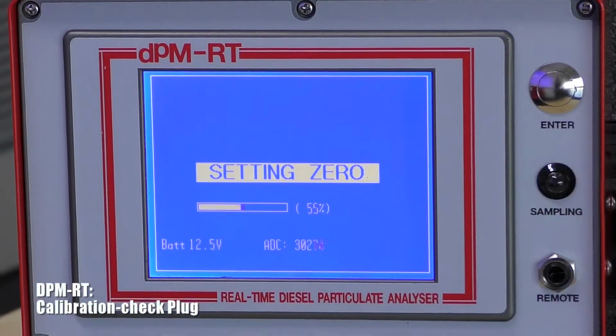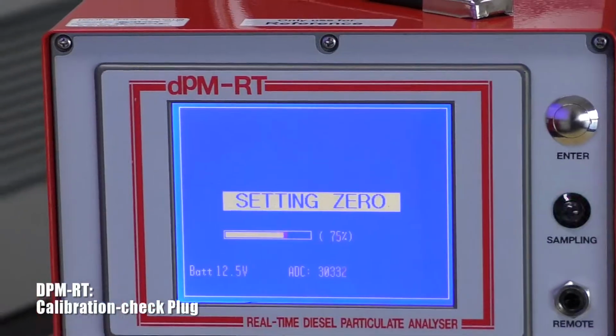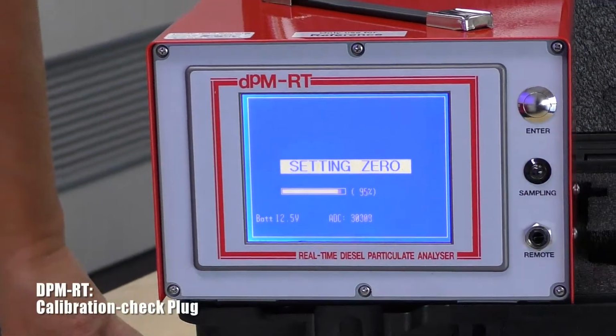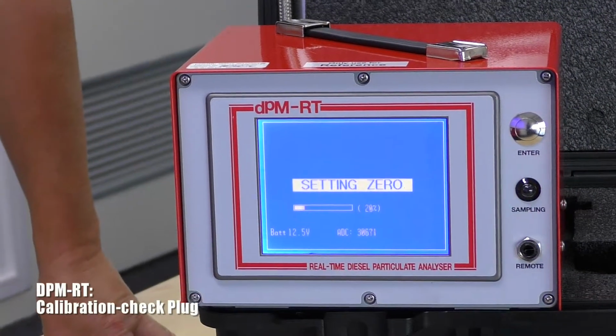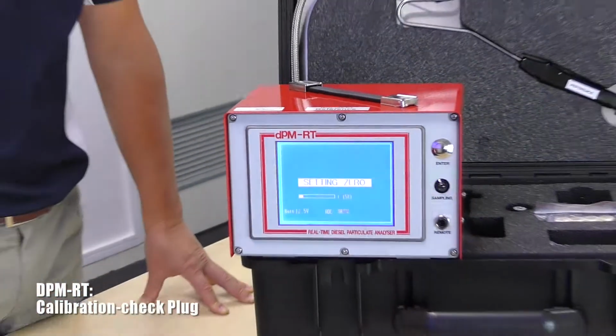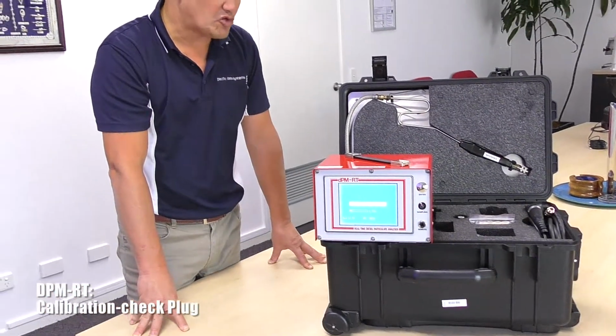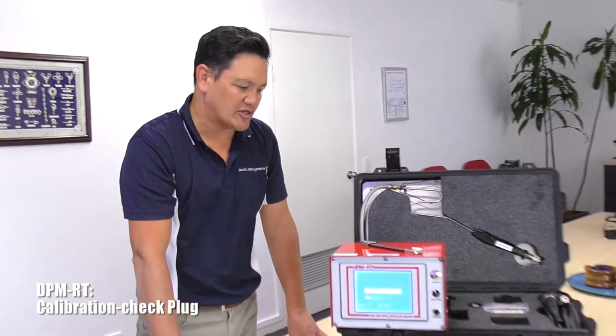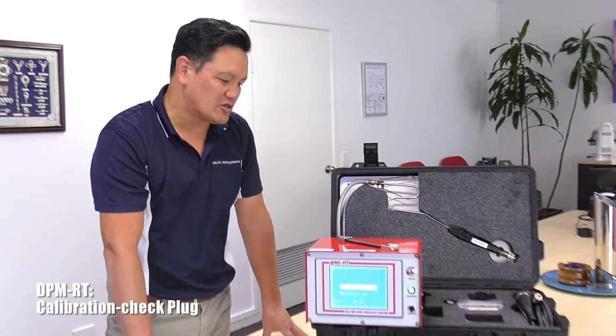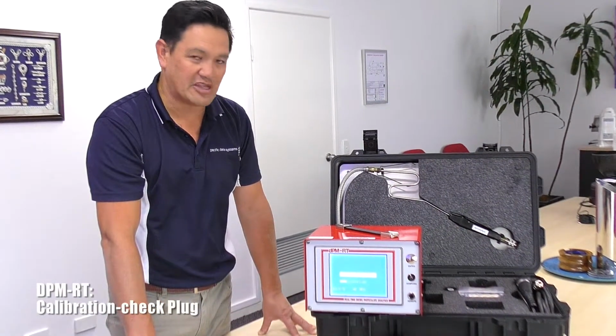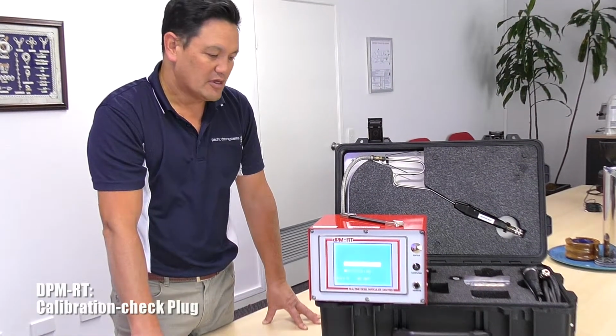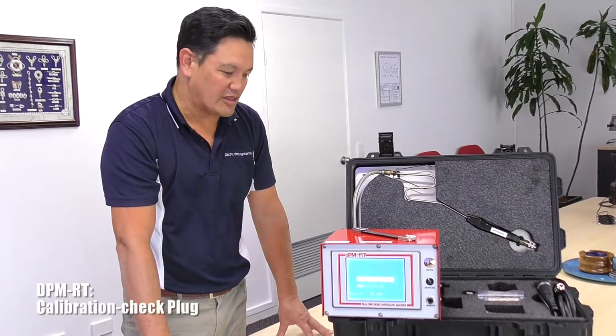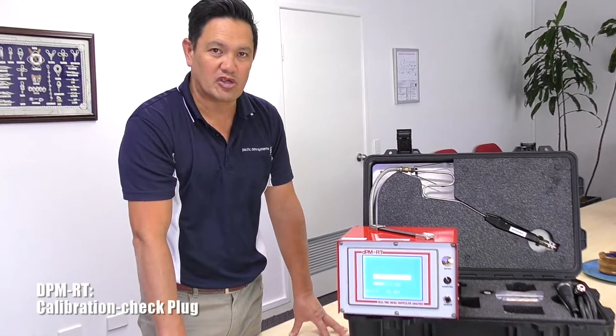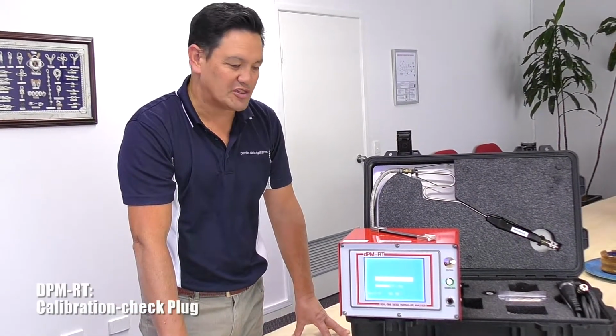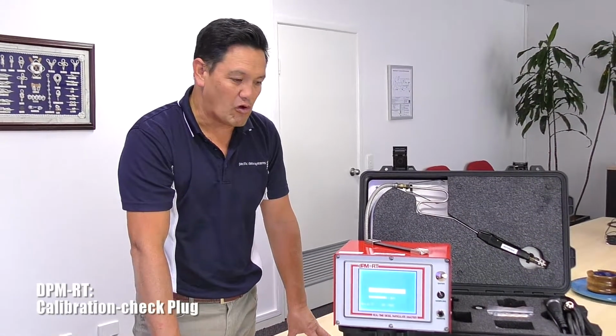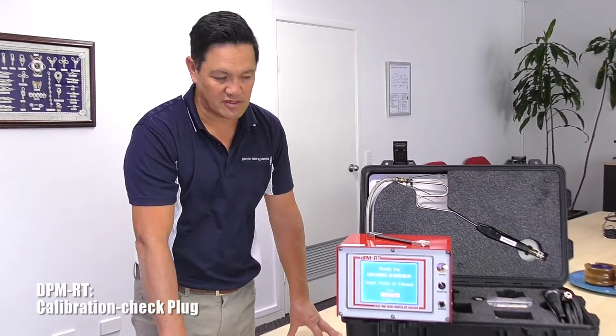The calibration check plug is specific to the instrument supplied. Therefore, if the calibration check plug is lost for any reason, you'll need to send the instrument back so a new calibration check plug can be manufactured and calibrated against that particular check plug. It is still recommended that the instrument is sent back to your local service centre or us, Pacific Data Systems Australia, the manufacturer, for a 6-monthly service.